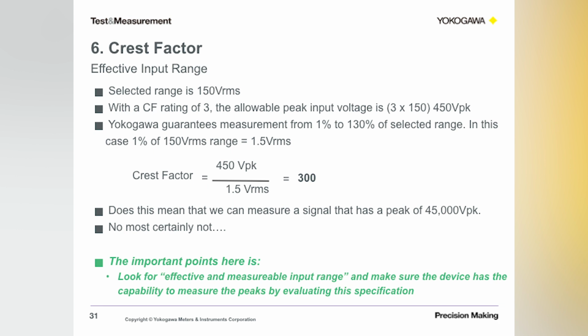So as an example, if we select the 150 volts RMS range with a crest factor of 3, the allowable peak would be 450 volts peak. But if the instrument can measure down to 1% of range, which is 1.5 volts RMS, then based on that definition, the crest factor would calculate out to be 450 volts divided by 1.5, that's 300.